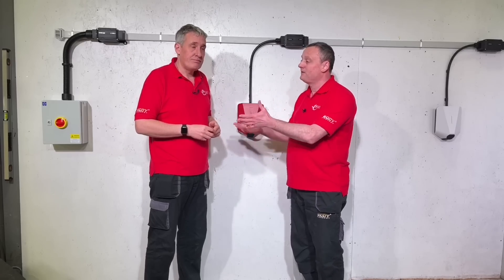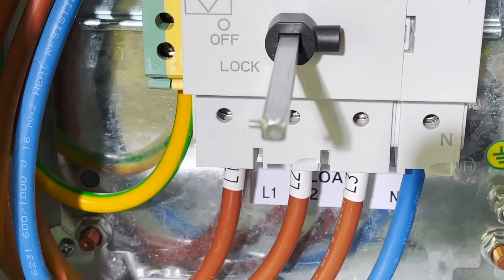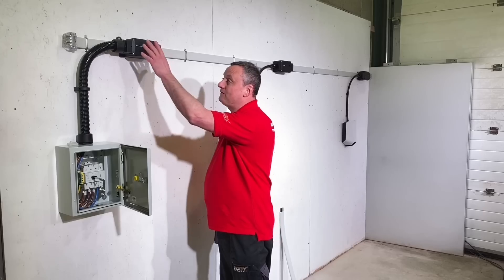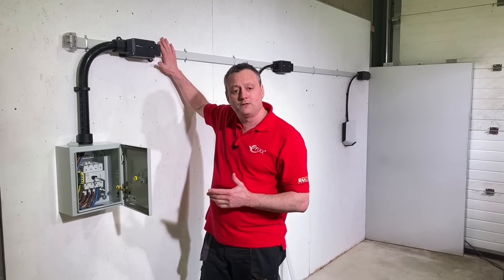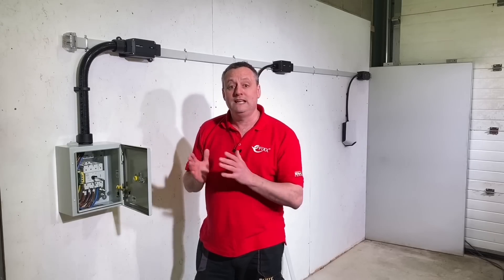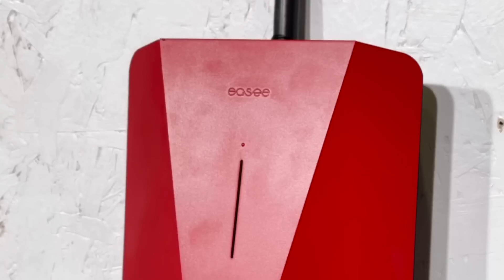We've installed this installation behind us — let's go through the key parts. Here we are at the origin of our installation where we pick up our supply. From here we've wired three-phase, neutral, and protective conductor in 16mm² tri-rated cables through flexible conduit into our junction box. The connections are made in the junction box, but the clever part is how we connect from the junction box onto the bus bar — it's screwed in, so we don't need to strip and terminate the bus bar. The Easee chargers are really clever: they'll never exceed the incoming supply fuse and will communicate between each other to share the load.